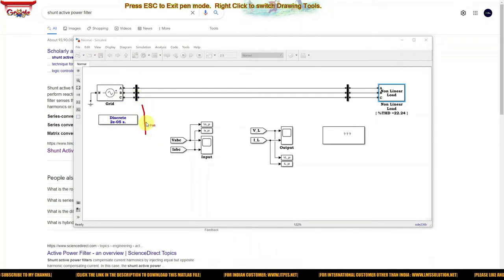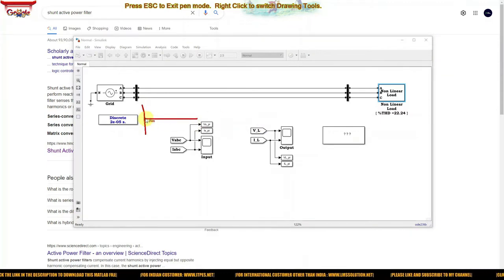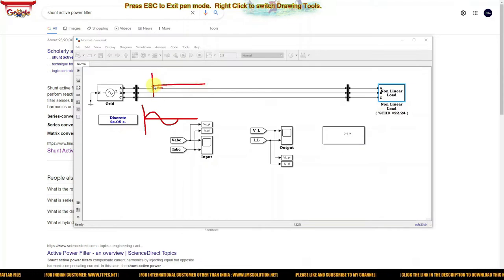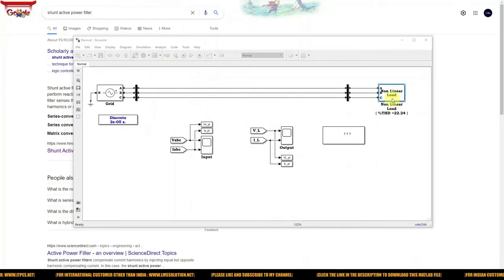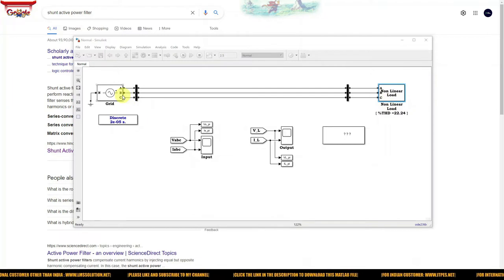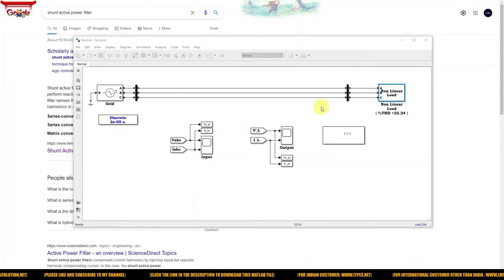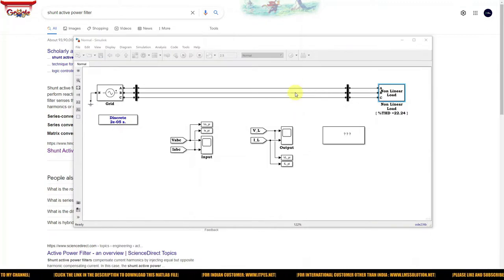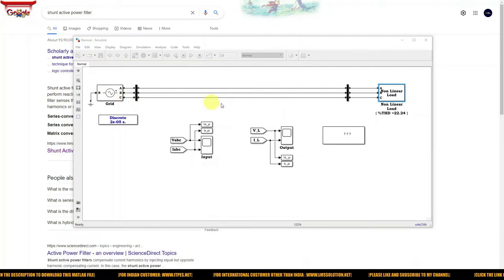Normally, when you connect a linear load, the source current is sinusoidal. But when you connect a non-linear load, the source current becomes non-sinusoidal. Because of this non-linear load, reactive power is consumed from the grid, and we need to compensate that reactive power by injecting a compensating current to the grid.